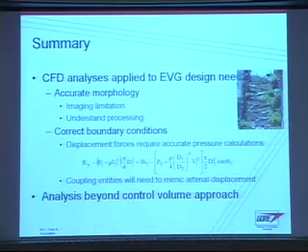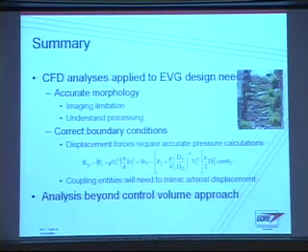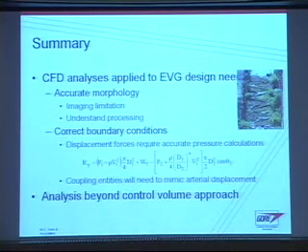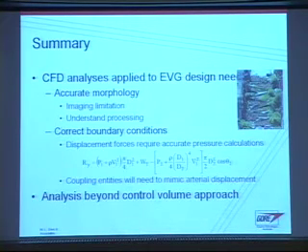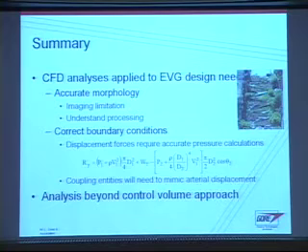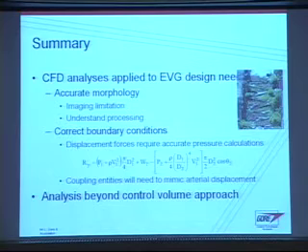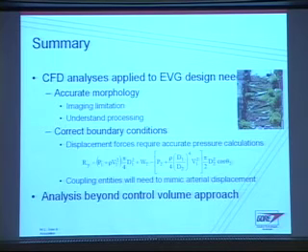In summary, for CFD analyses and how it can be applied to endovascular graft needs: the first is the need for accurate morphology and taking that into consideration. There's been some talk today about imaging modalities, and keeping in mind when you're looking at limitations — if you're trying to measure a displacement that is within your resolution, can you actually say that you're measuring a displacement force? Displacement forces require the use of accurate pressure calculations. Pressure is going to be a driving force regardless of what you're looking at for a displacement, and using an accurate outlet boundary condition is going to help in that prediction.